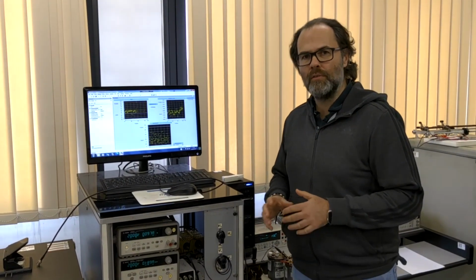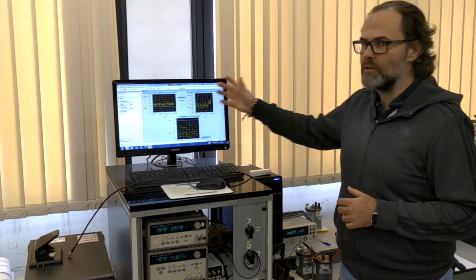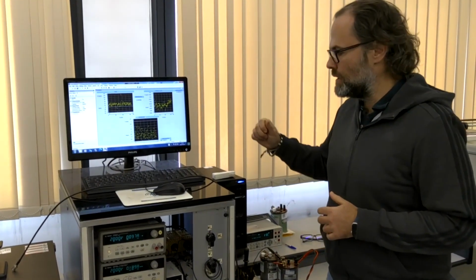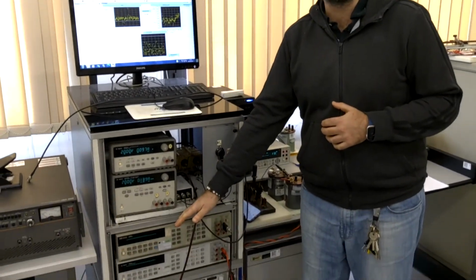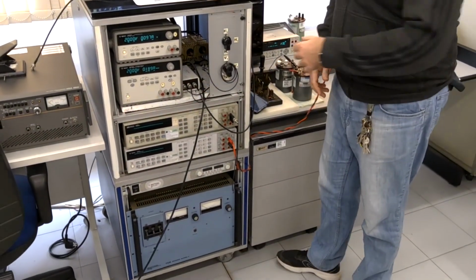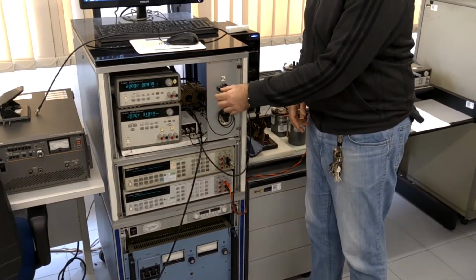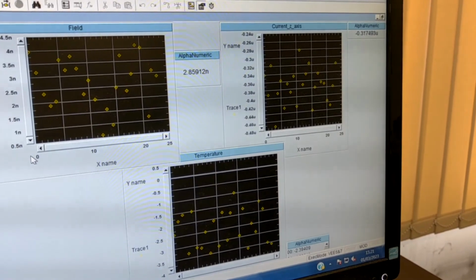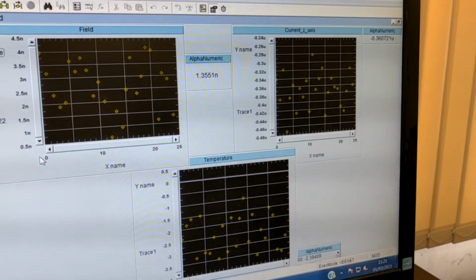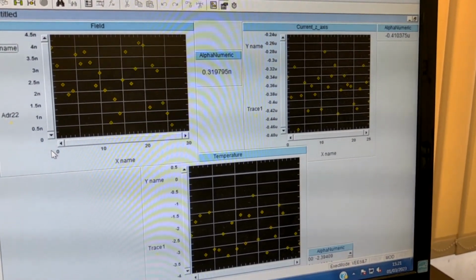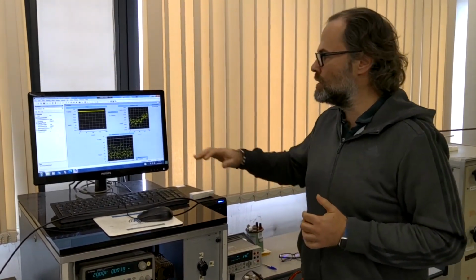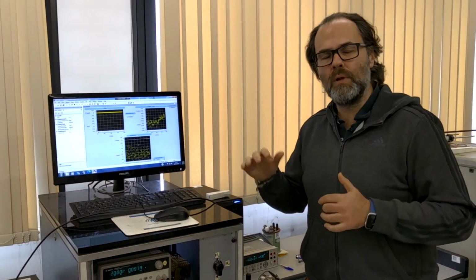The actual process of compensating the Earth magnetic field is done through a software that has been developed in-house. The software interfaces with a multimeter that has the reading of the Flux-Gate sensor, and through a switch can switch from the X component, Y component, and Z component of the Earth magnetic field measured with the Flux-Gate sensor. The software allows us to change the current value that flows into the 3 Helmholtz compensating coils, in order to keep the residual value of the magnetic field measured with the Flux-Gate sensor below the threshold value of 30 nanotesla along all 3 directions, X, Y, and Z.